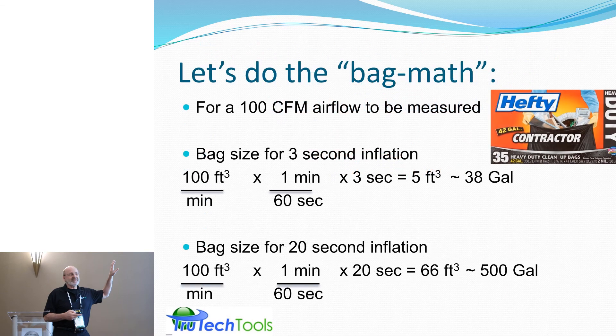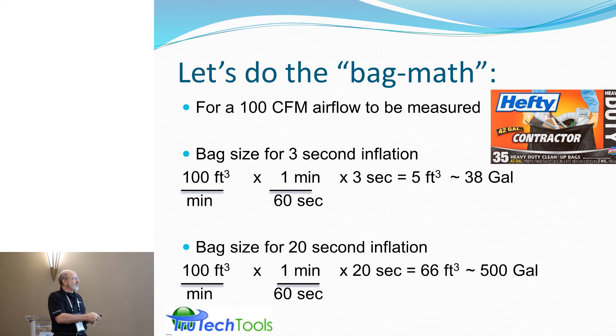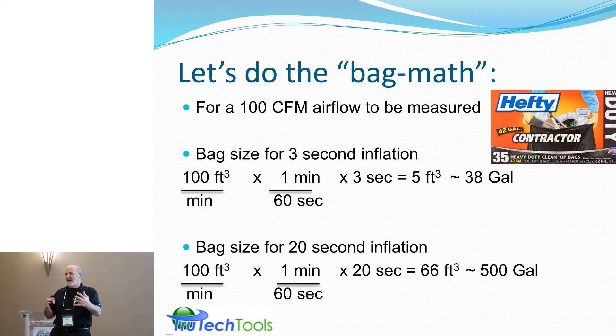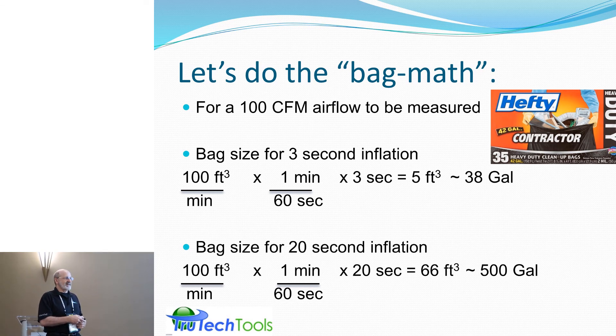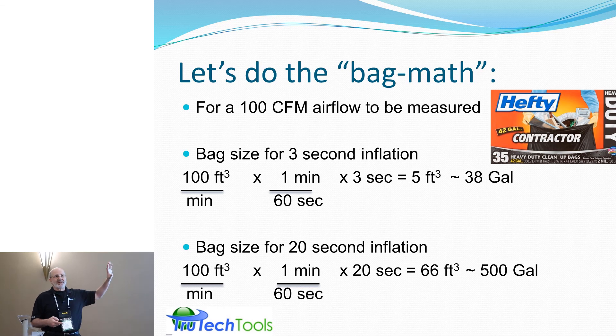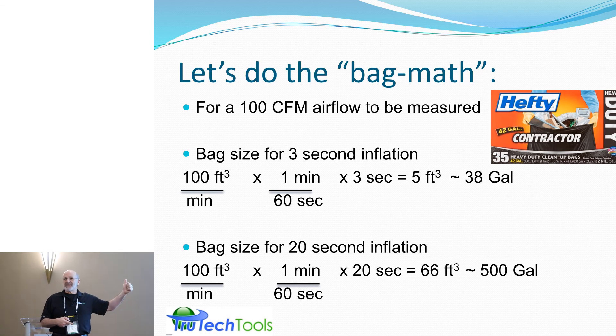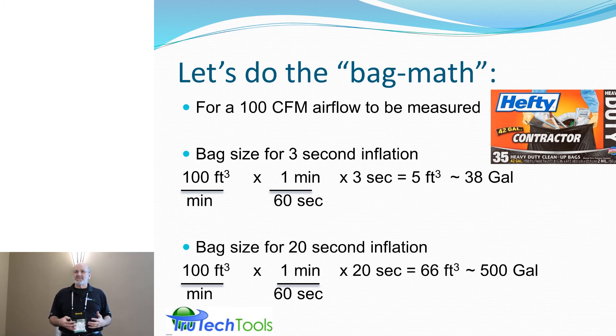Doing the bag math: for 100 CFM airflow, it works out to a 38-gallon bag, which seems reasonable — contractor bags are in the 35 to 42-gallon range. But they're pretty heavy and thick, which will impact consistency. For a 20-second inflation, it's a 500-gallon bag — I challenge you to fill that with water and measure it. You also need a stopwatch for the bag inflation method. This part of the standard seems like it should be revisited.